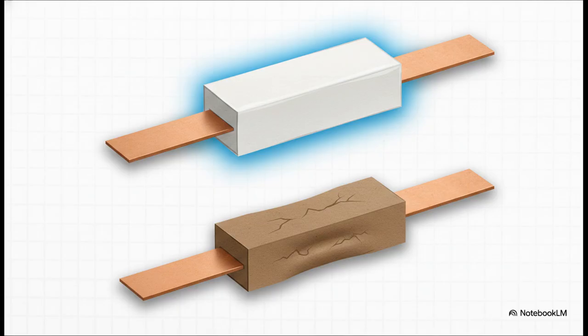Next up, we've got the Comparative Tracking Index, or CTI. This explains why the exact same voltage can require completely different creepage paths depending on the insulator you use. A higher CTI number basically means the material has way better resistance to electrical tracking. Group I materials like your ceramics and thermosets are incredibly resistant. What that means is if you use a high-quality Group I material, you can mathematically justify shorter creepage paths than if you went with a weaker organic Group 3 surface, even under the exact same electrical stress. So yeah, picking good materials literally saves you space.